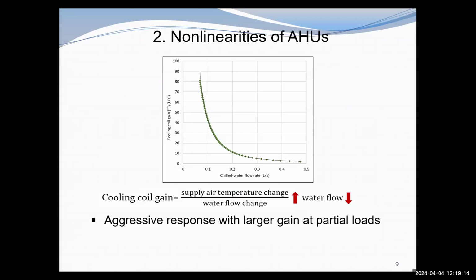And the component gains, for example, the cooling coil gain. This figure shows the cooling coil gain variation with the chilled water flow rate. We can see as the chilled water flow rate decreases, the cooling coil gain increases, especially at low chilled water flow rate. The cooling coil gain increases dramatically here. And for the control system, the system will have an aggressive response with larger gains at these partial load conditions, with a very large gain.